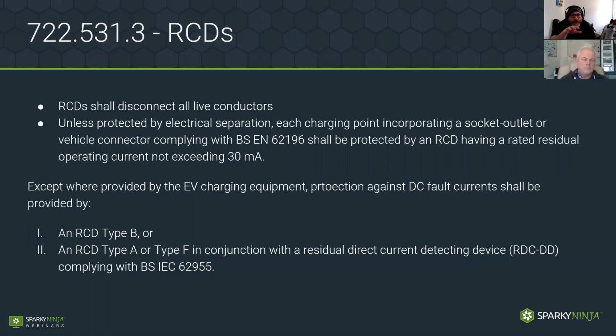Now, unless the electric vehicle charging equipment has protection against DC fault currents internally, then we need to think about DC currents. Now, with my work with the E5 guys, we've been talking about DC leakage into the AC network a lot, and we've been stressing about the need to consider type A RCDs over type AC RCDs, and we can see that demonstrated here. So it actually says we want to think about type B as our first choice. We could use a type A or type F in conjunction with, this is a fun one, a residual direct current detecting device, an RDCDD, complying with BS IEC 62955, an RDCDD.